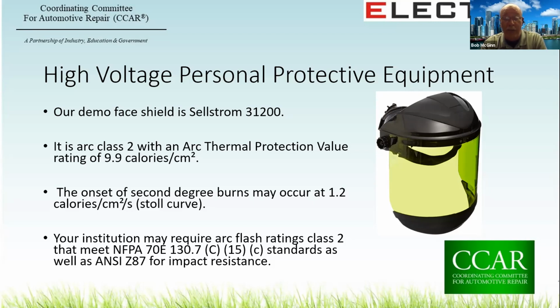And we all remember from our science days as children that the calorie is the energy required to raise 1 gram of water 1 degree Celsius at 1 atmosphere. That's great. It doesn't mean anything to me. Or possibly that the onset of second-degree burn may occur at 1.2 calories per square centimeter per second. That's the Stoll curve. Still doesn't mean anything. How about this? This was conveyed to me by an engineer, a very smart man: you can approximate 1 calorie per square centimeter per second to be equal to holding your finger over the tip of the flame of a cigarette lighter for 1 second.